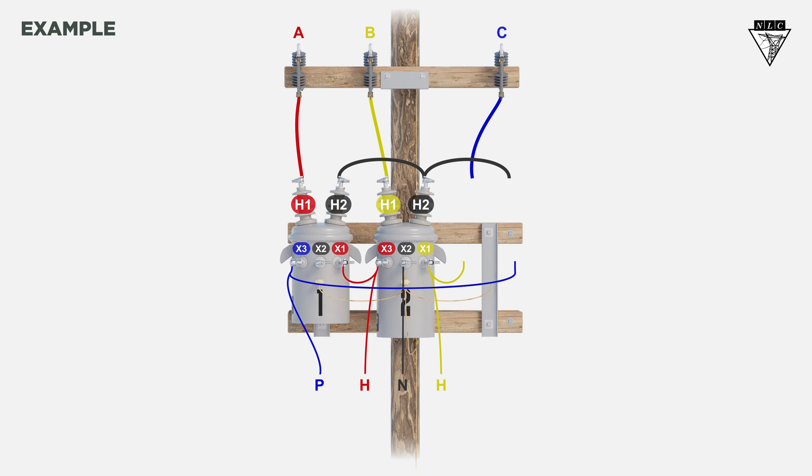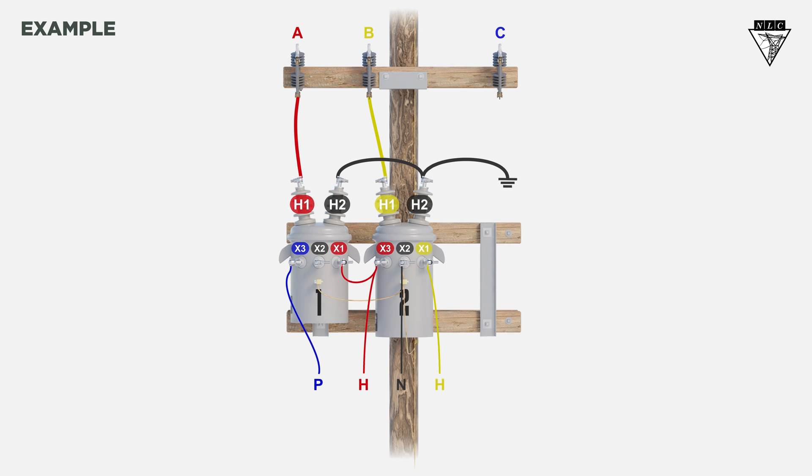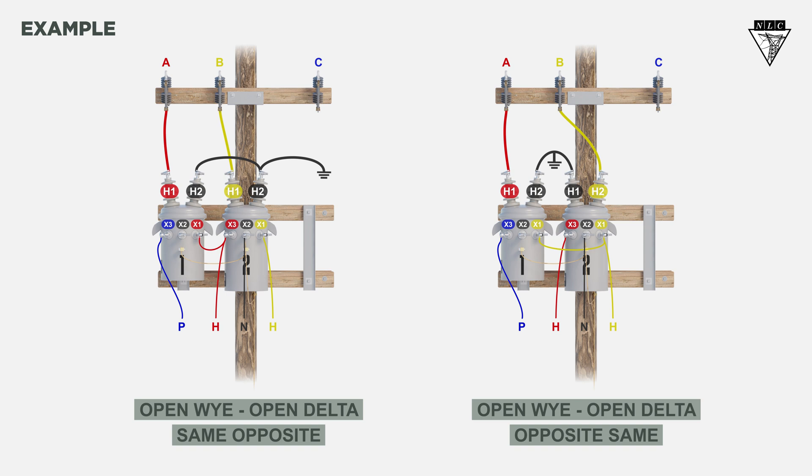Additionally, since a Y-delta bank is a bank of single-phase units, they can be reconnected as an Open Y Open Delta to supply power to the customer temporarily before a permanent solution is made. There are two ways to connect an Open Y Open Delta on the secondary side. To learn more, check out our Open Y Open Delta Banks video.